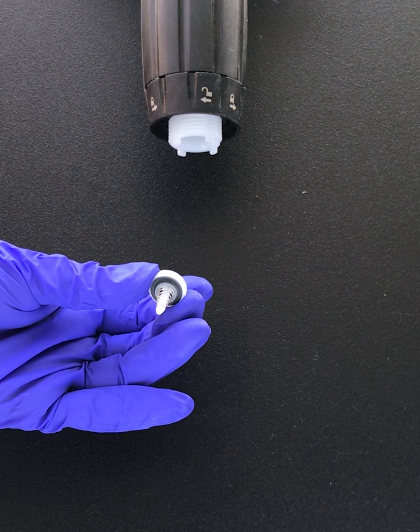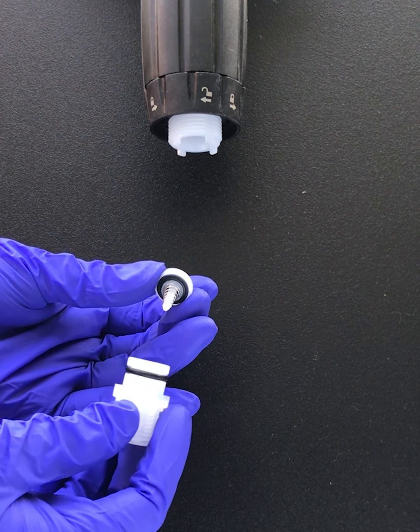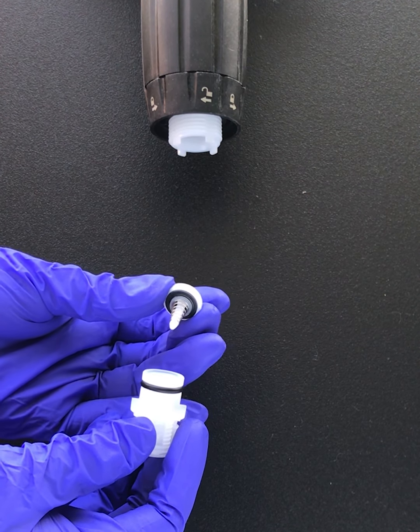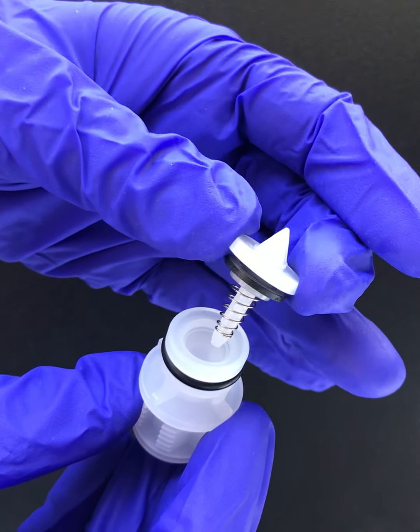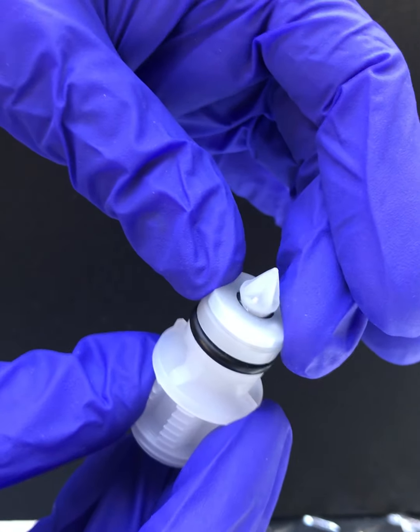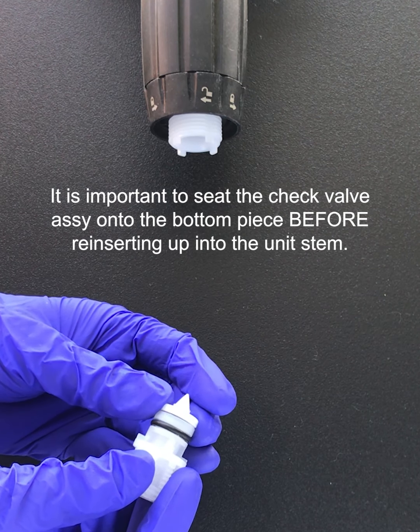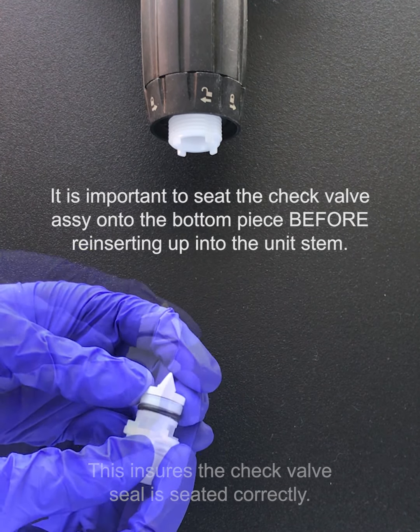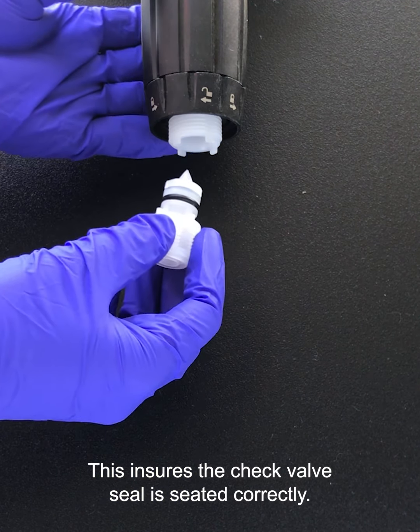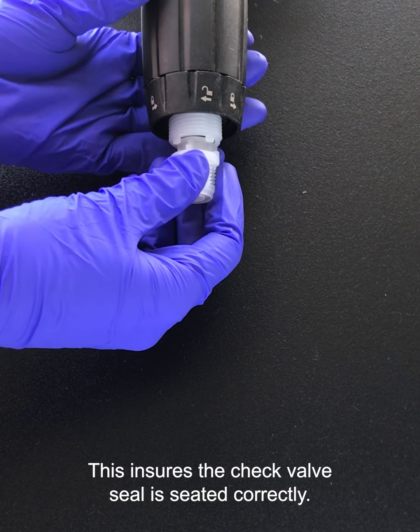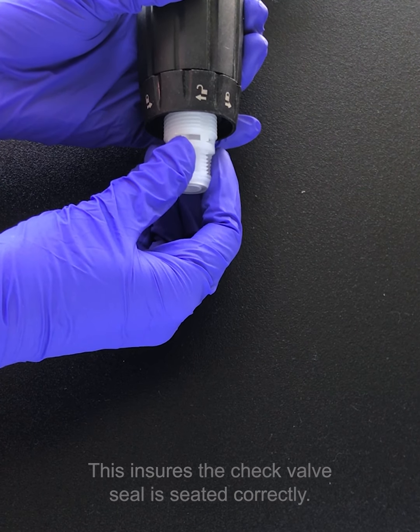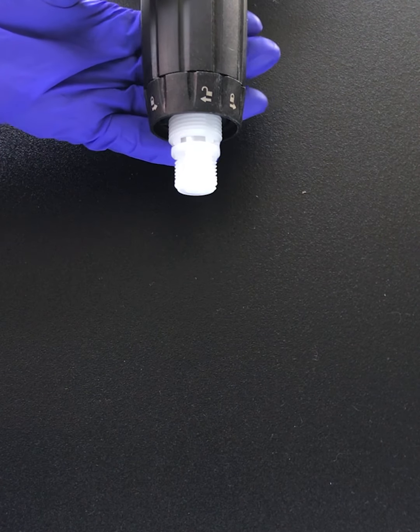In order to do so, you need to reinsert the spring downward first, like so, making sure the black seal is sitting properly on the groove. You can wiggle it to make sure it is on there correctly. Then it is time to reinsert it into the bottom of the stem assembly, like so. You will feel the O-ring locking into place. Reattach the check valve and tighten hand tight.